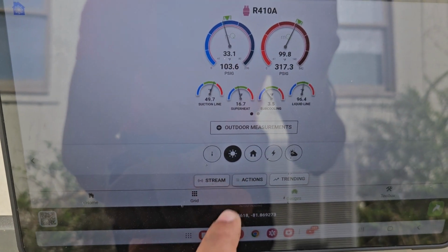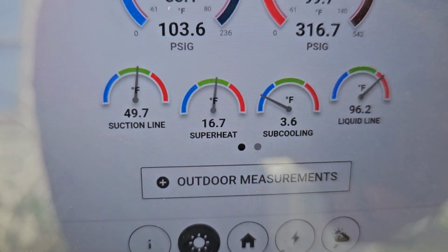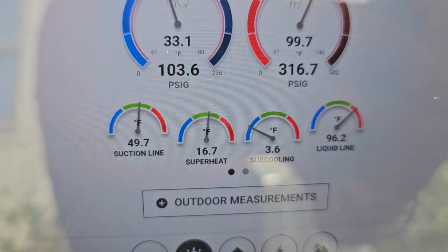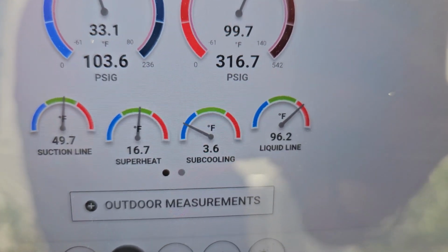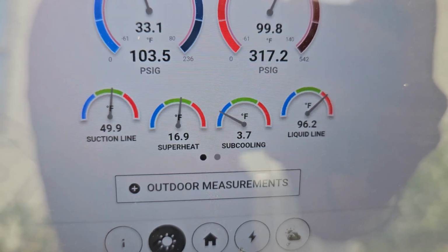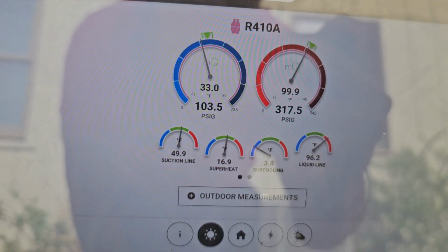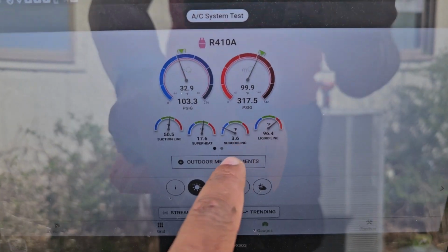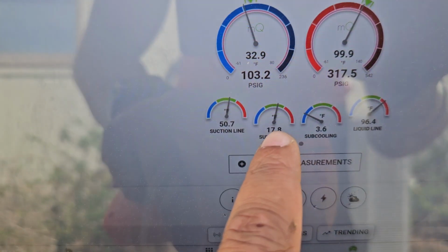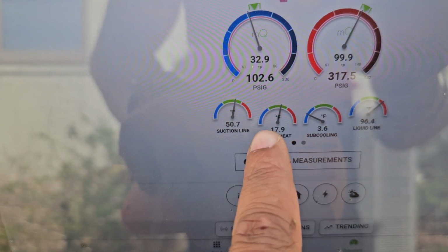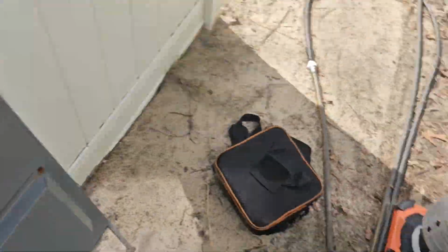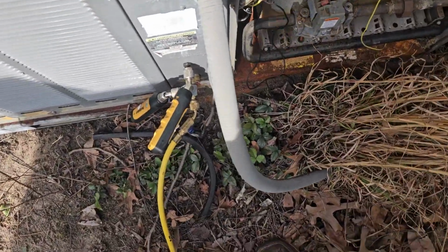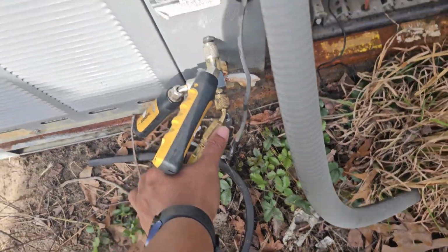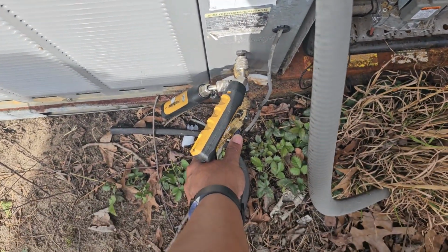Let's go back here, look at the superheat. The superheat's looking a lot more optimal, subcooling still low. I'm gonna try and drop in about another half pound, see if we can't raise that subcooling up, at least get it into the green, and make sure the superheat doesn't fall out of the green, because that would be more along the lines of not necessarily good.